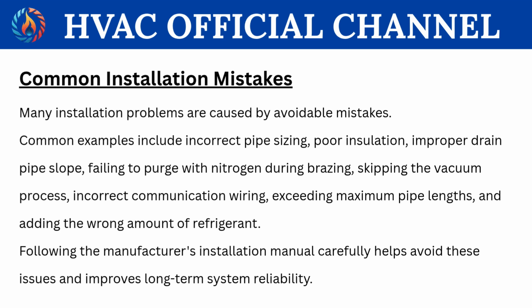Common installation mistakes. Many installation problems are caused by avoidable mistakes. Common examples include incorrect pipe sizing, poor insulation, improper drain pipe slope, failing to purge with nitrogen during brazing, skipping the vacuum process, incorrect communication wiring, exceeding maximum pipe lengths, and adding the wrong amount of refrigerant. Following the manufacturer's installation manual carefully helps avoid these issues and improves long-term system reliability.